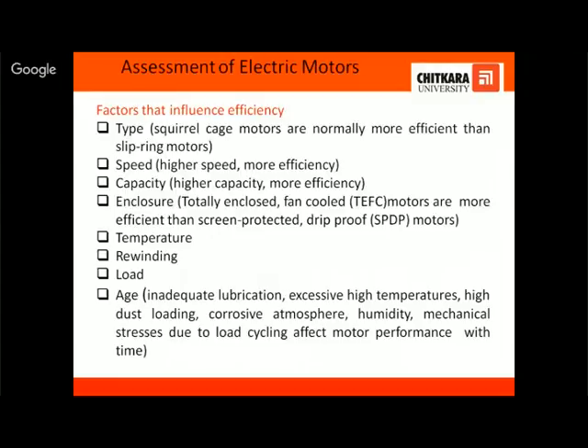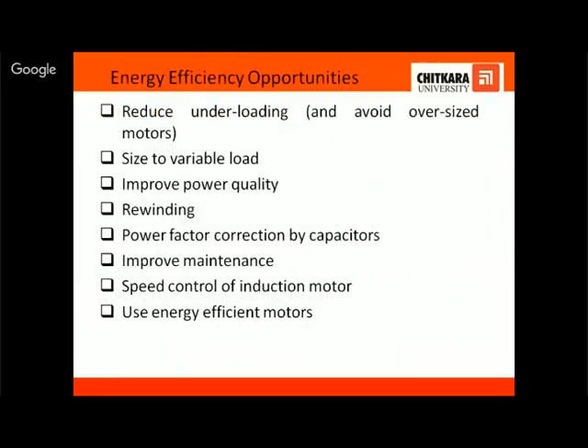Then, if there are excessive high temperatures, the age of the motor gets reduced. If there is a dusty environment, a humid environment, or mechanical stresses due to load, all these things affect the age of the motor. Otherwise, if all those things are perfectly fine, the motor works for 20-30 years, it's not an issue. Now, I had discussed the main factors which are affecting the performance of the motor.